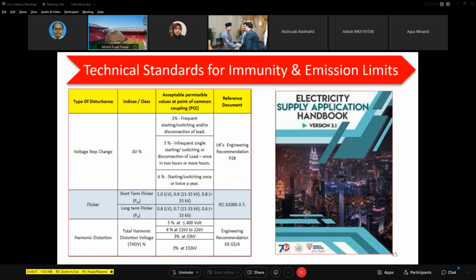First of all, to ensure less emission. We don't want the customer to emit transient. We don't want the customer to emit flicker. We don't want the customer to emit harmonics. These are the limits to ensure that the emission complies with the requirement. For example, if equipment starts very frequently, the voltage must not be distorted, increased or decreased, by more than 1%. This is very critical. But if the equipment is operated every 2 hours or more, the voltage must not be distorted by more than 3%. But if the equipment is operated only once or twice a year, then 6% is allowable.